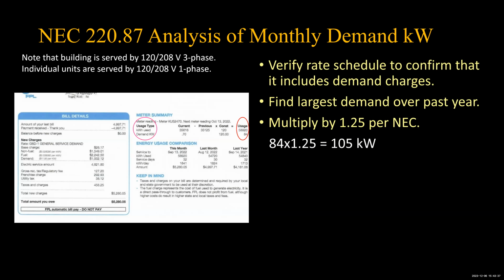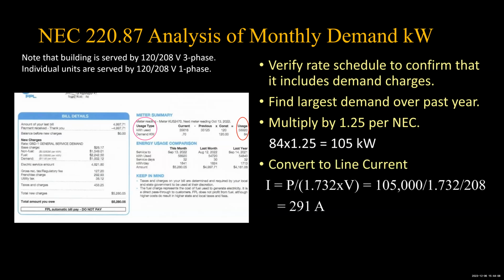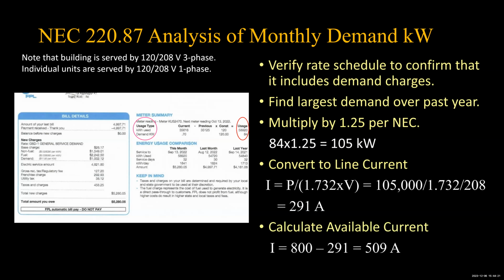Multiply that by 1.25 because that's what NEC says you have to do. So instead of 84 kilowatts, we've got 105 that the building is at. Because when you're doing the actual measurement from the meter, you have to take 125% of that to be conservative enough. And so we got 105, and then we divide that by 1.732 times the line-to-line voltage, and we get 291 amps. So that means 291 out of the 800 amps are committed to the building, but that leaves 509 amps left over as available for EV charging.